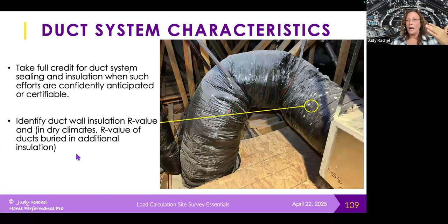So we want to take full credit for duct system sealing and the insulation when those efforts are confidently anticipated or certifiable. We're going to identify duct wall insulation. So in an existing system, we need to find where it says on the ducts what the R value of those ducts is. Buried ducts in dry climates are fantastic, and so those ducts have an even higher R value. And so we would put that in if we know the ducts are going to be buried.